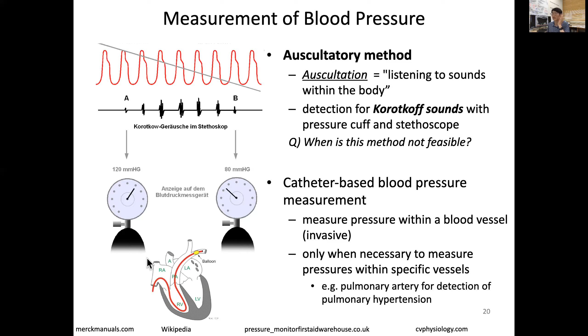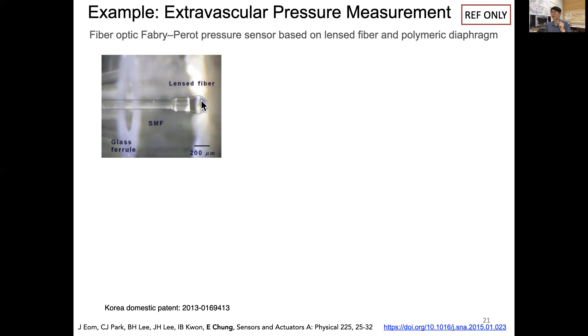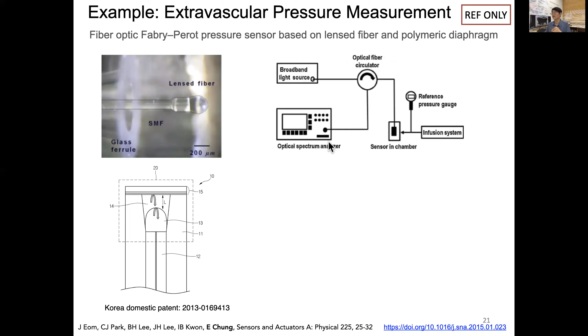I want to give you an example of extravascular pressure measurement, which I happened to be involved in: making a fiber-optic Fabry-Perot pressure sensor based on a lensed fiber and a polymeric diaphragm. We created an optical fiber where the light goes in, and a lensed fiber was made. That fiber reflects from a polymeric diaphragm that responds to pressure. The tiny displacement can be measured by optical interference, detected by an optical spectrum analyzer with a broadband light source. To create the lensed fiber we used an electric arc discharge to shape it like a lens. We published this and generated patents.